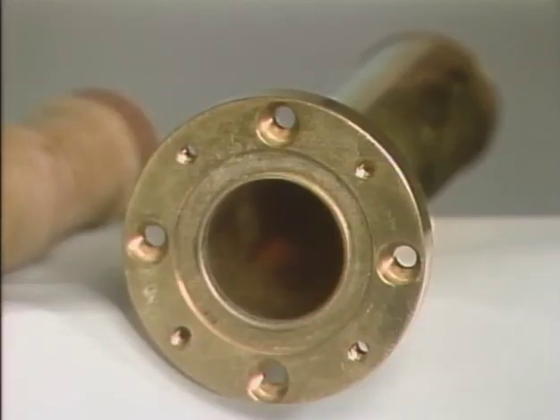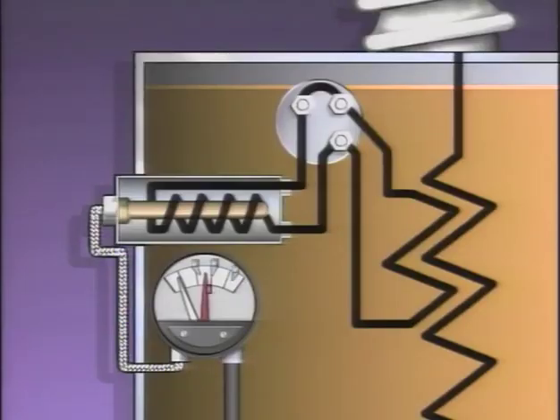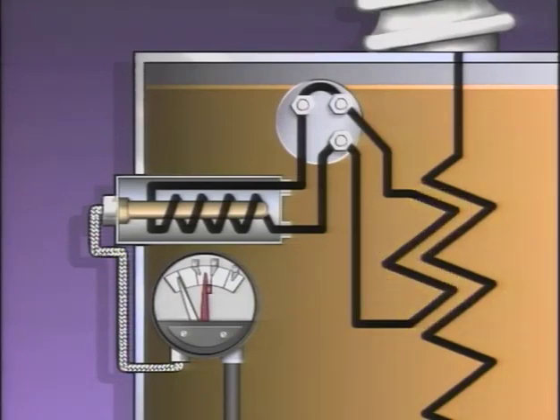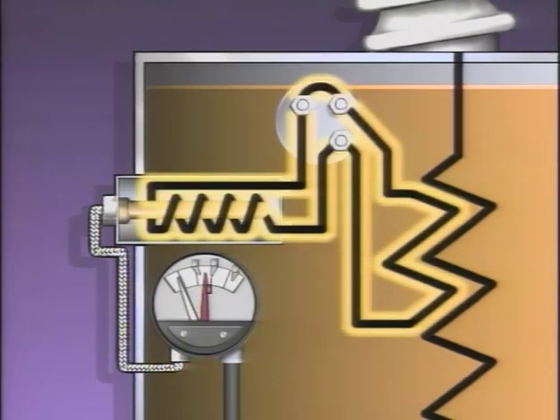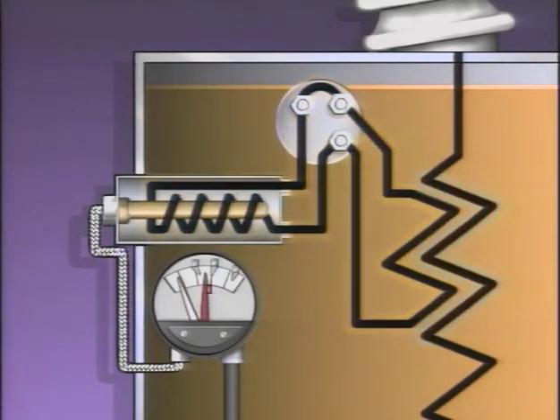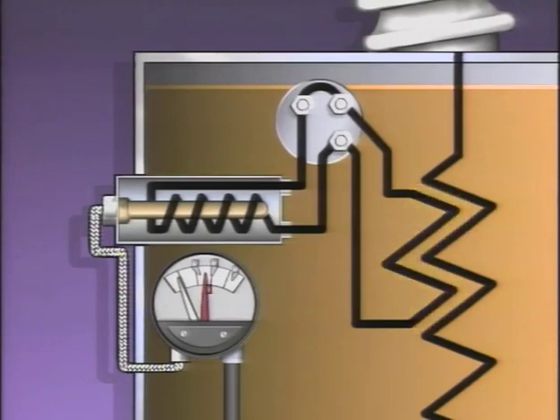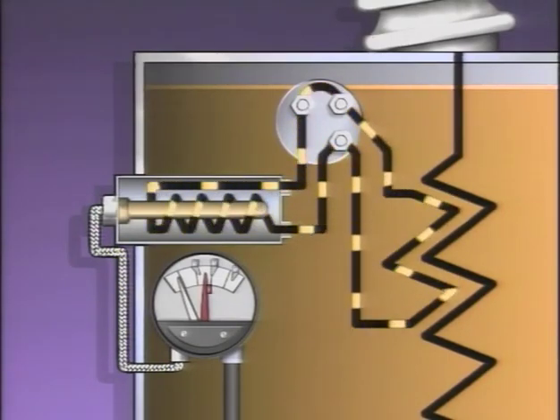The function of the heating element can be explained using an illustration that includes a power transformer winding, a current transformer, a terminal block, a heating element, a temperature-sensitive bulb, capillary tubing, and the winding temperature gauge. The heating element is connected to the secondary of the current transformer, which surrounds part of the power transformer winding or winding lead. The current transformer provides a current that's proportional to but much lower than the load current of the power transformer.